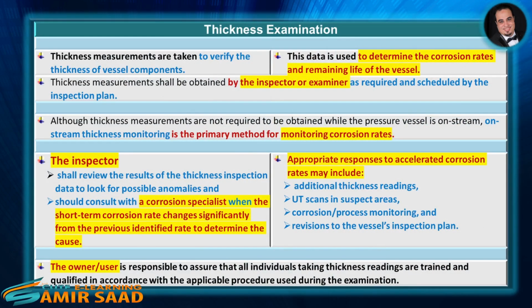Thickness examination. Thickness measurements are taken to verify the thickness of vessel components. This data is used to determine the corrosion rates and remaining life of the vessel. Thickness measurements shall be obtained by the inspector or examiner, as required and scheduled by the inspection plan.